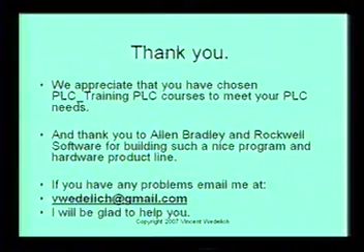So if you're thinking about designing a product line, manufacturing something, seriously consider these Allen Bradley products, because what I've done is I've taken the Allen Bradley MicroLogix and I've put it in a simulated test, and I just sat there turning large motor starters on and off trying to break this controller. It didn't break the controller. You know what it did? It broke the motor starter. So the motor starter's mean time between failure was much less than the controller's.